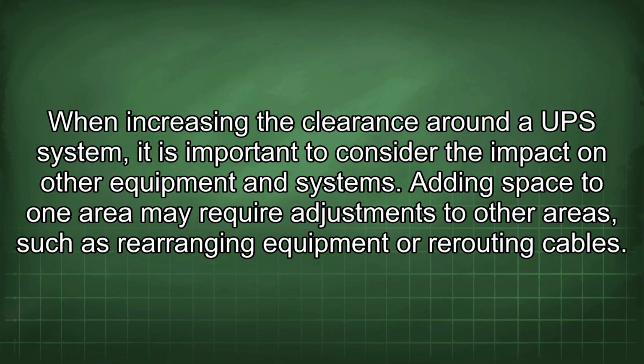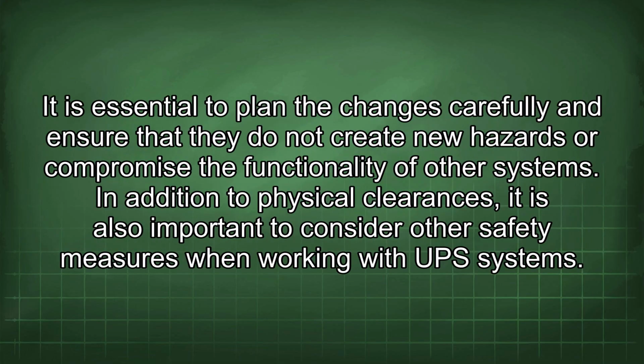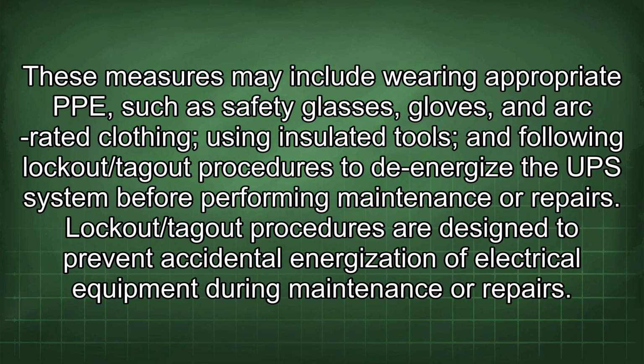When increasing the clearance around a UPS system, it is important to consider the impact on other equipment and systems. Adding space to one area may require adjustments to other areas, such as rearranging equipment or rerouting cables. It is essential to plan the changes carefully and ensure that they do not create new hazards or compromise the functionality of other systems. In addition to physical clearances, it is also important to consider other safety measures when working with UPS systems. These measures may include wearing appropriate PPE, such as safety glasses, gloves, and arc-rated clothing, using insulated tools, and following lockout/tagout procedures to de-energize the UPS system before performing maintenance or repairs.